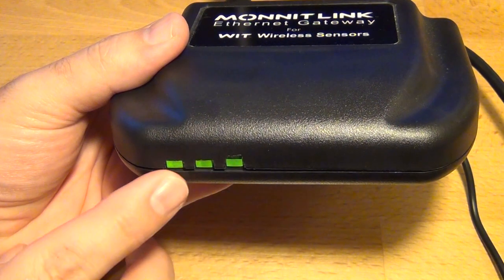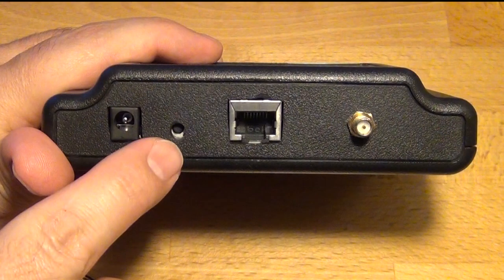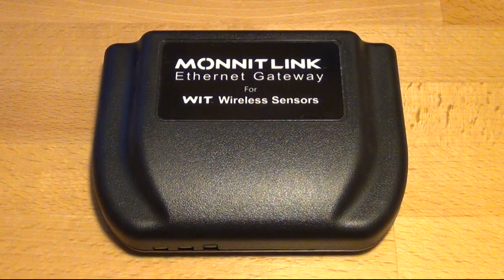If you need to reset the Ethernet gateway to the factory defaults, press and hold the reset button on the back panel of the Ethernet gateway for 5 seconds, or until the lights turn off and then back on. Note that this will not update the settings on the iMonnit server; it will only reset the gateway to the factory default settings.